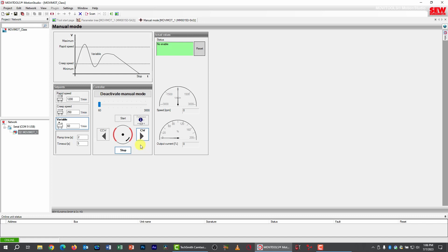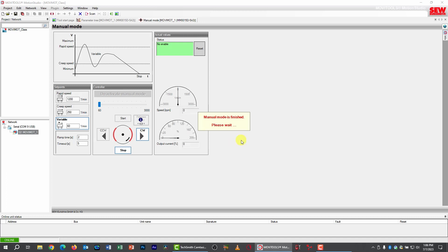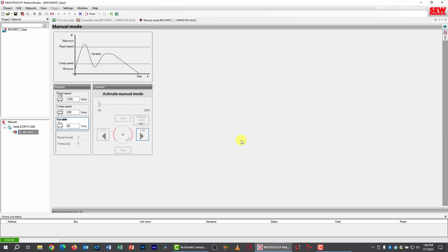I want to go to the parameter tree and take a look at a few things here. In order to do that, I have to deactivate manual mode, so I'm going to click the deactivate button. And this is a very good place to mention that you should never leave manual mode activated because it essentially disables the drive from normal operation. So always deactivate it when you're done with it. And it always gives you this little warning that if something is turned on, it is possible the motor could just run when manual mode releases. Since I have a demo unit and my switches are all off on my control box, I know nothing's going to happen. So I'll click yes here to exit.